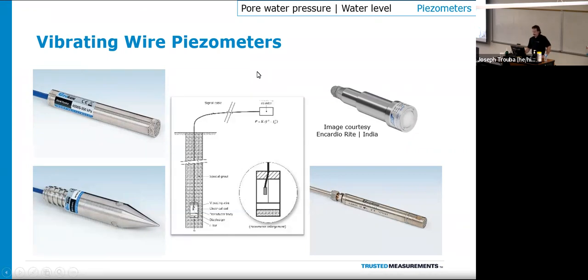So inside you have this little vibrating wire, your magnetic assembly around it. As the pressure from that formation or water body is pushing on that diaphragm, it's going to shorten and elongate that vibrating wire based on the pressure it's feeling. So where it's installed, how that water level or pressure is fluctuating, that can be recorded with this instrument. And again, it's basically plucked with that magnetic plucking coil, and that frequency is sent back to a data logger, which can then be converted to pressure measurement or water level measurement with calibration.